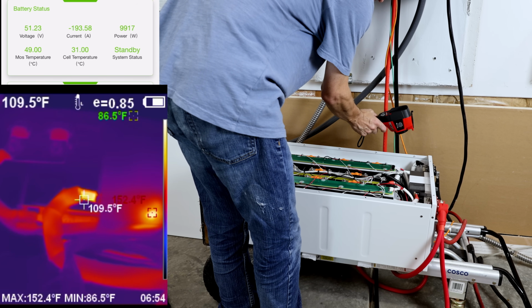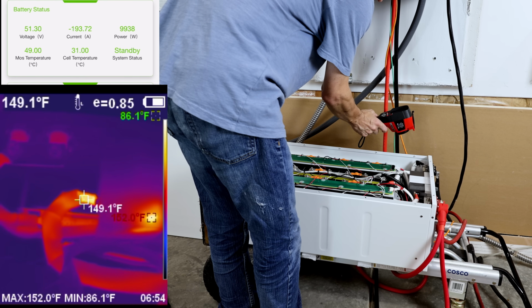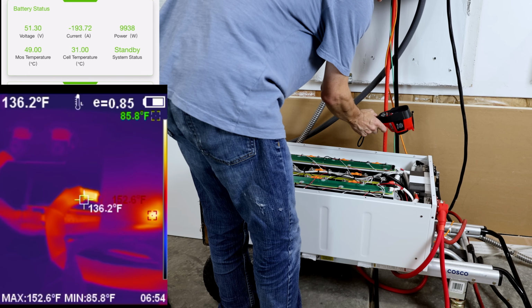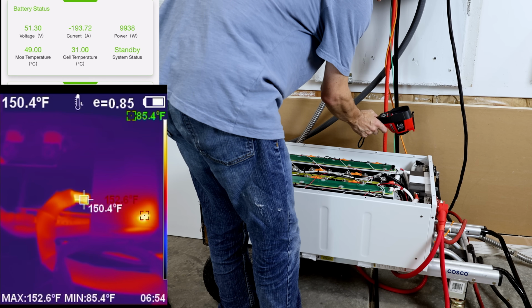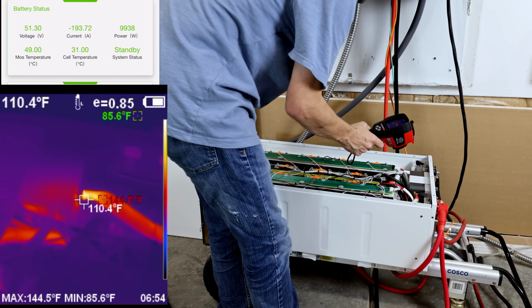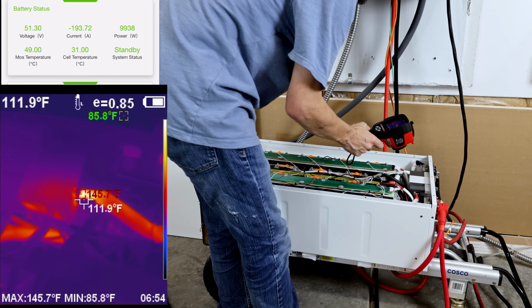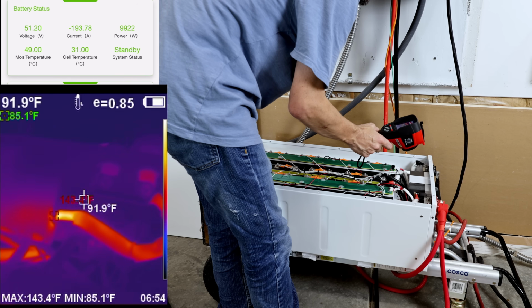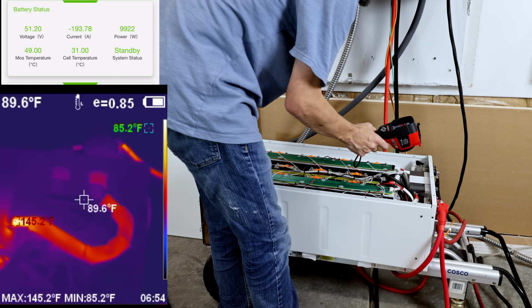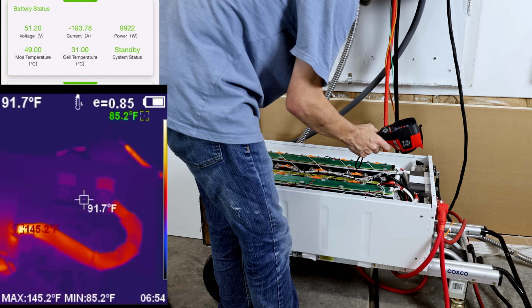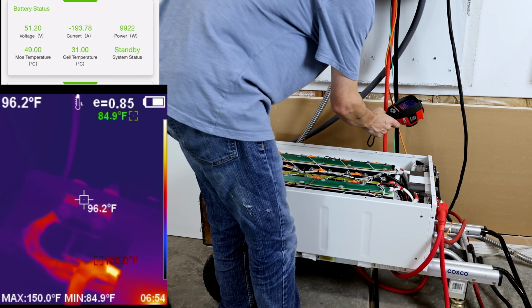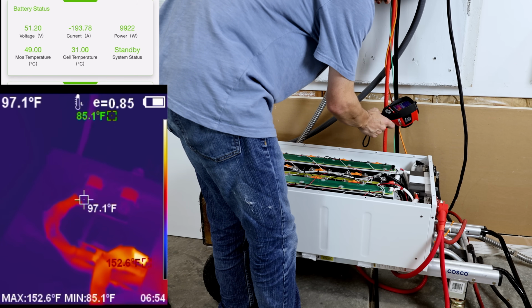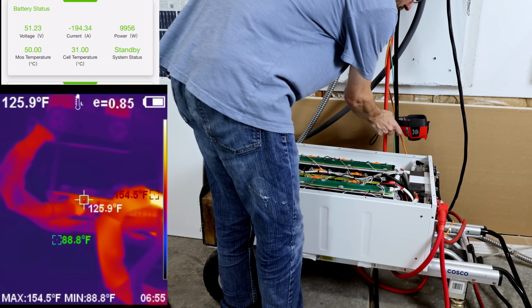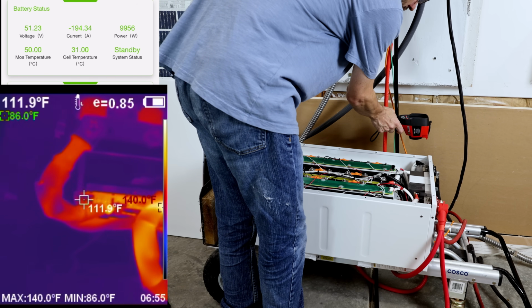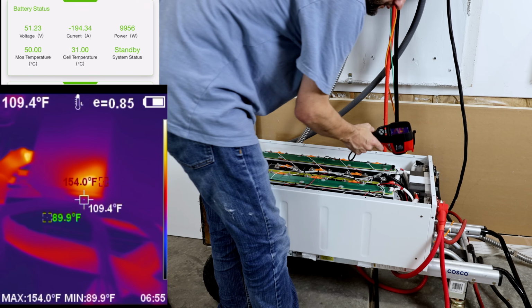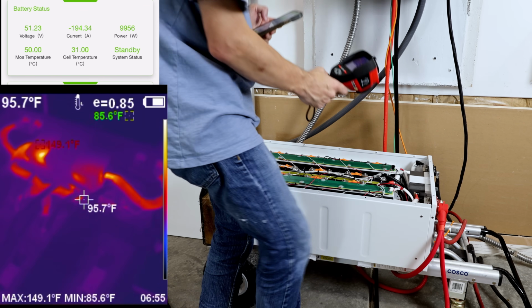Got about 150 Fahrenheit there on the input and output to the breaker. The bus bar is cold. Nothing crazy hot down there on the BMS. That all looks pretty good.